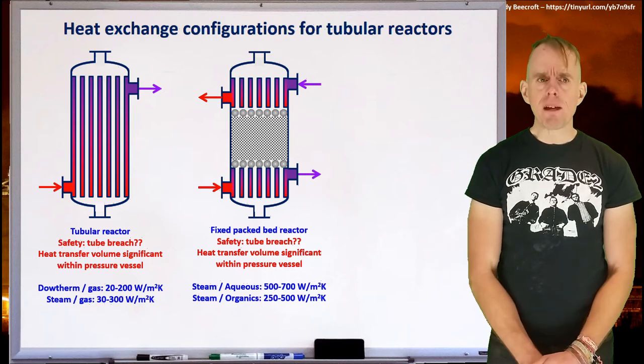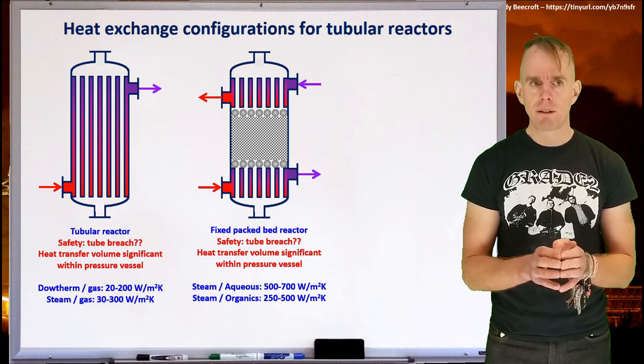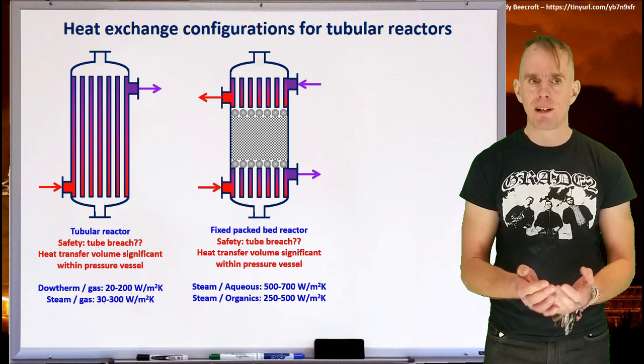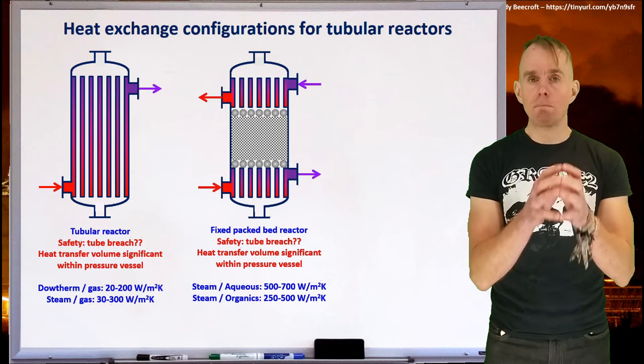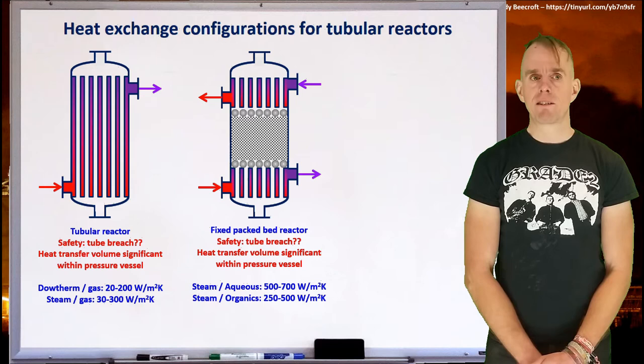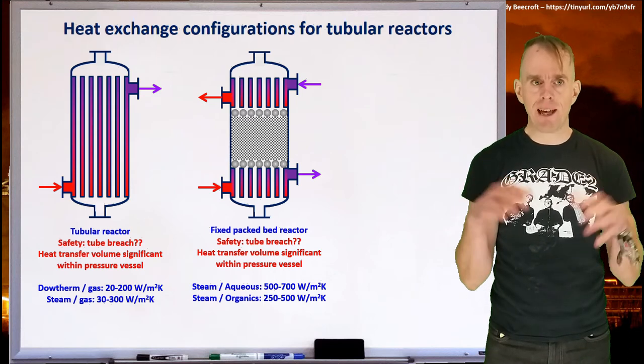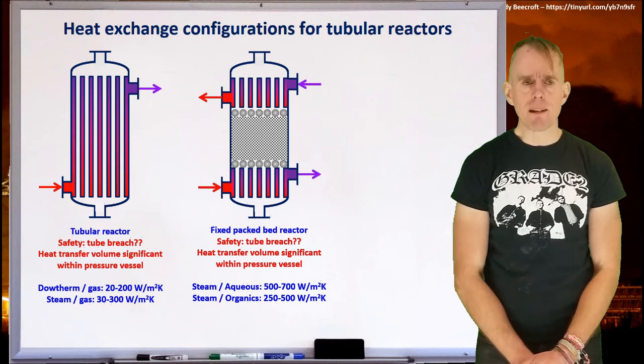And so the second diagram is kind of similar to that. What we have is a tube bundle within our pressure vessel. But this time, rather than taking the effluent of the reactor, it's taking an external utility. And then we have a second tube bundle that will be removing reaction exotherm. And again, that's illustrated with an external utility providing the heat transfer. So again, first thing to think about here is safety. We're using an external utility. What happens if you get a tube breach and you get the reacting mixture contacting the utility or the utility contacting the catalyst?